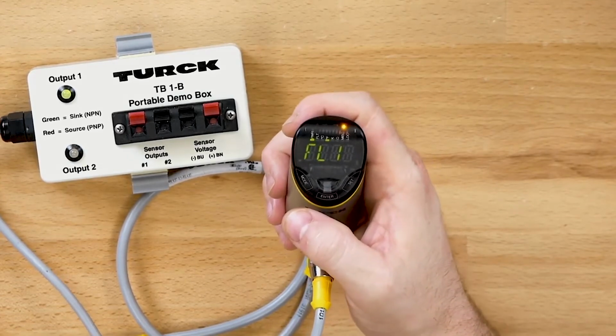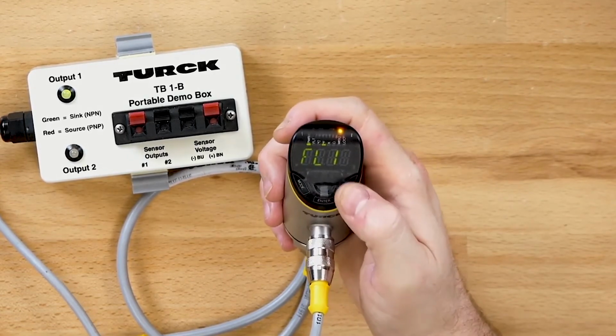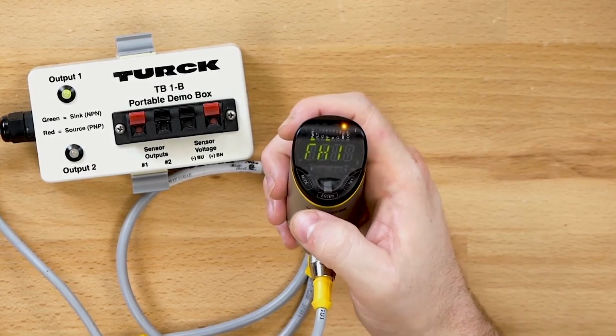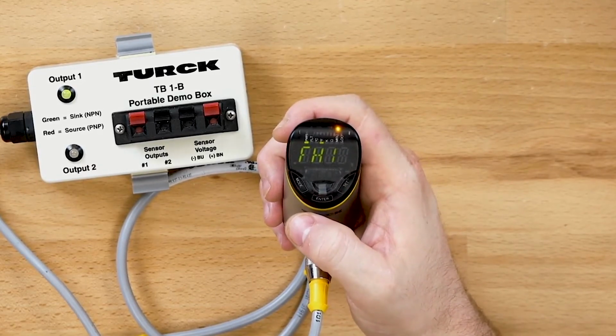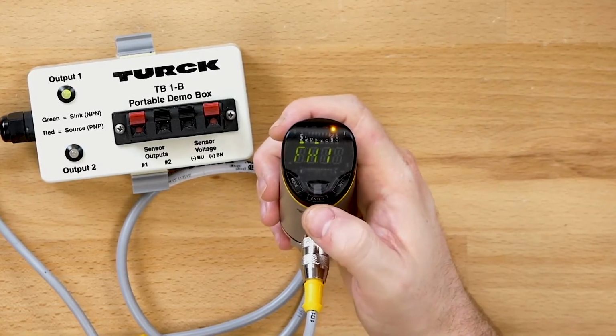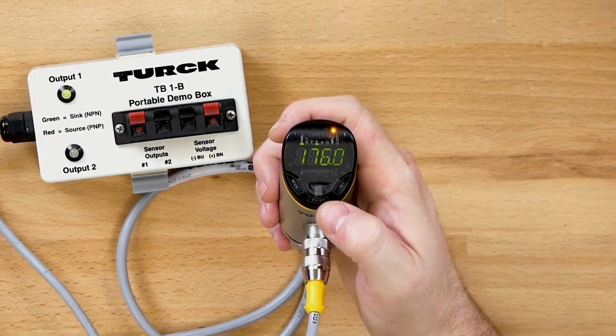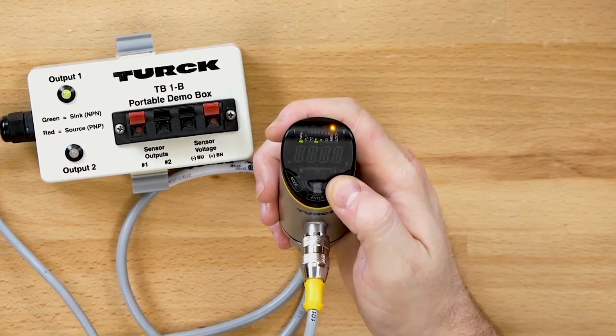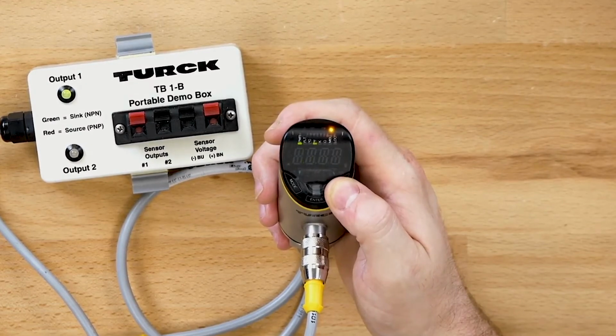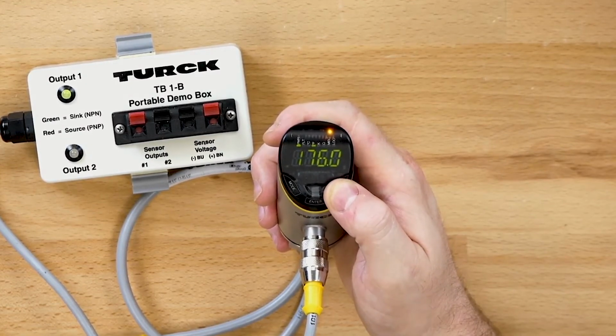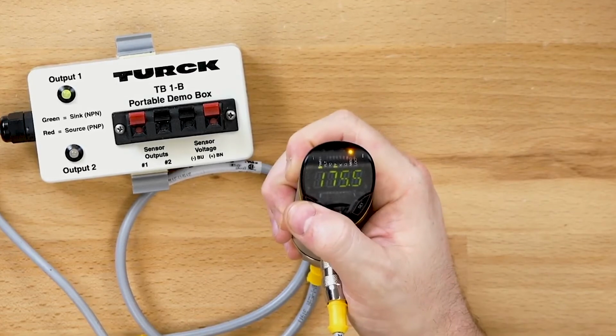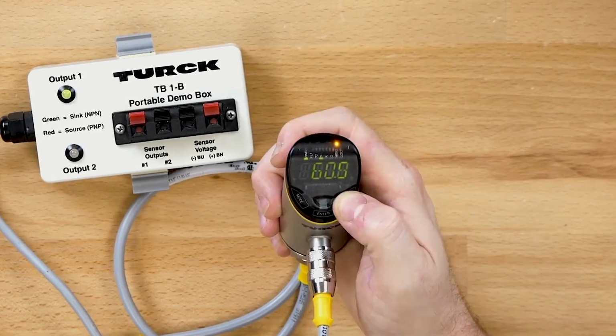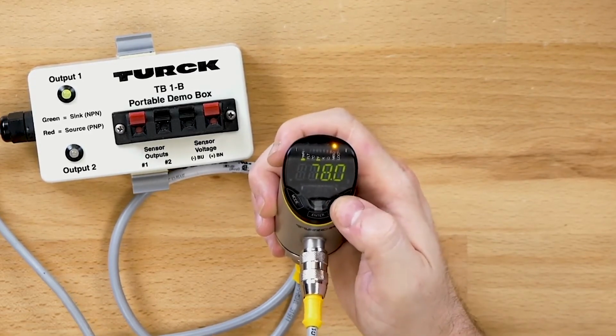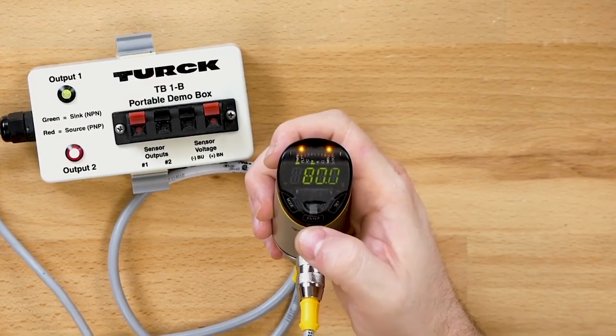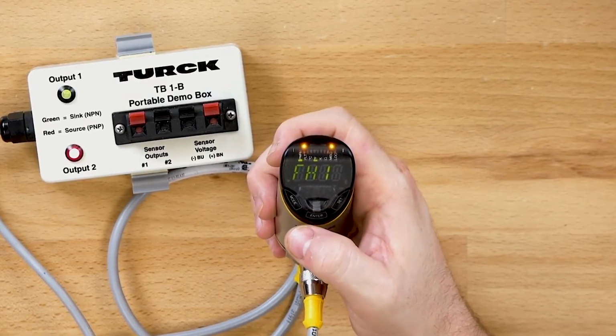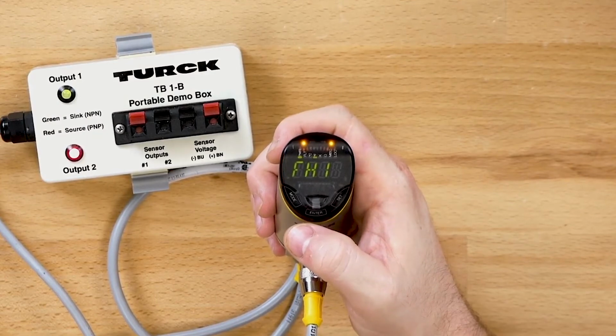Back in the main menu, let's navigate to the FH1 menu, which describes the upper limit of the window function for output 1. Again, using the Enter button to enter into the parameter selection, we're going to hold the Set button for 3 seconds until the display stops blinking, and then we're going to change this value to 80 degrees Fahrenheit. Again, pressing Enter to enter and store the parameter. The upper limit is now set.